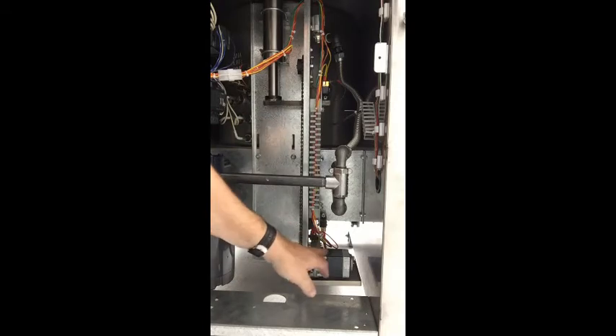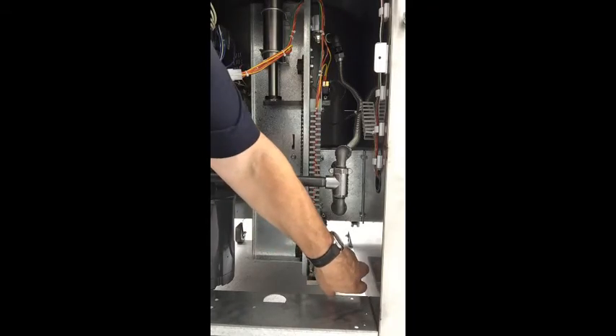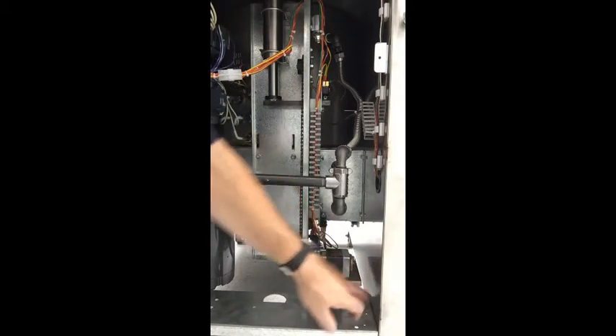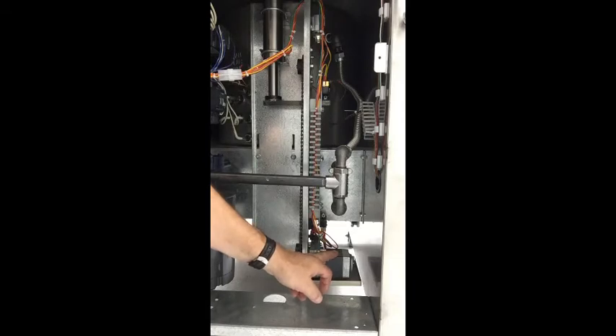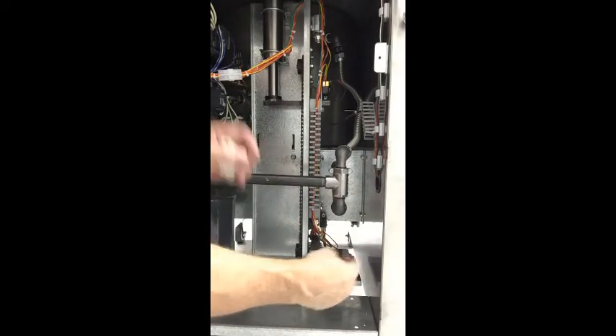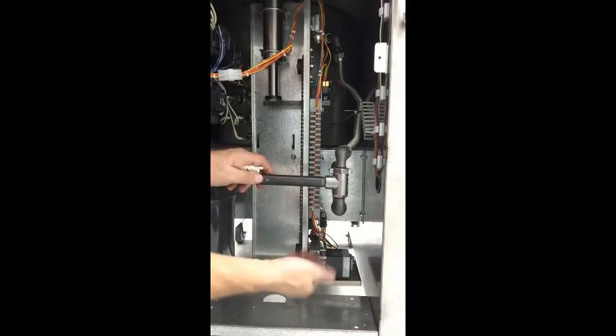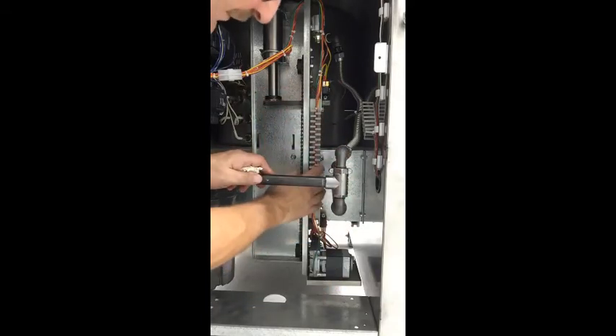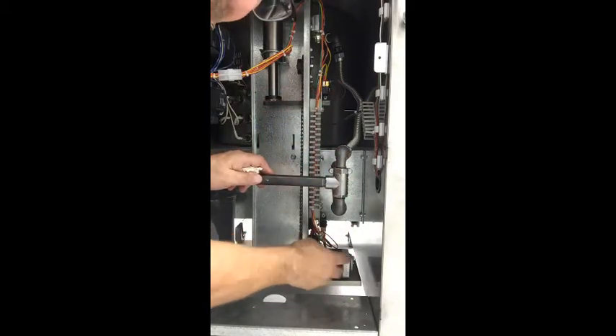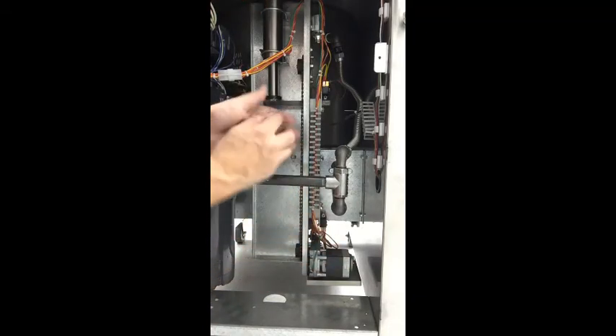But the basket elevator has this gear motor on the bottom. The gear motor actually has a brake inside of it. If you were to push on the shaft at the end, you can actually feel it. When we energize the armature, it releases the brake, which allows the motor to move. When you kill the power to the motor, that brake closes back up and seizes it and keeps it from turning.